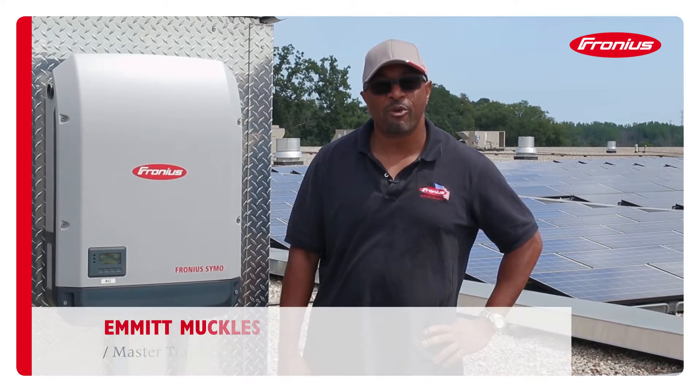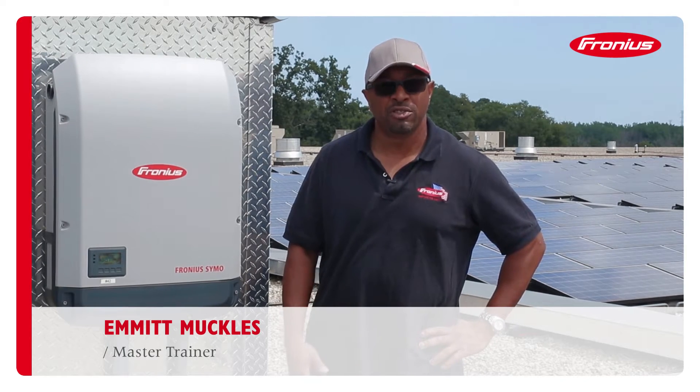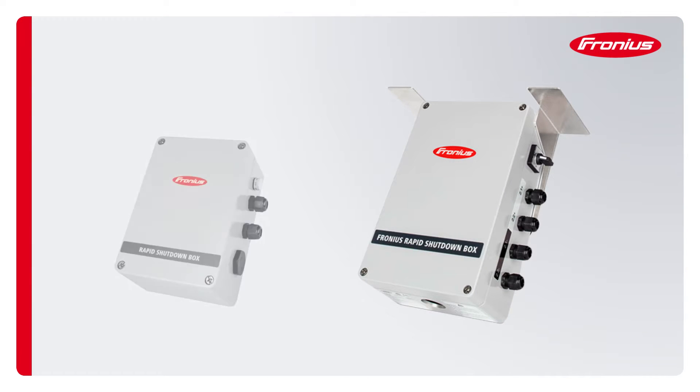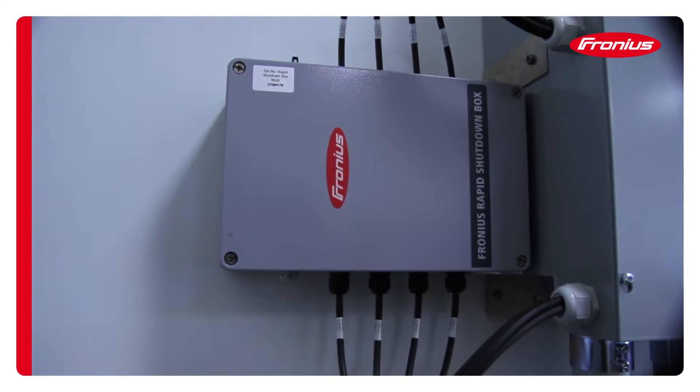Hey everybody, my name is Emmett, welcome to Fronius. Today I'd like to talk a little bit about our NEC 2014 rapid shutdown solution. We offer two products in that category: we have the multi-box and we have the single box. The Fronius rapid shutdown box offers a great solution — the 2014 NEC electrical code requires a PV system to shut down to 30 volts within 10 seconds.